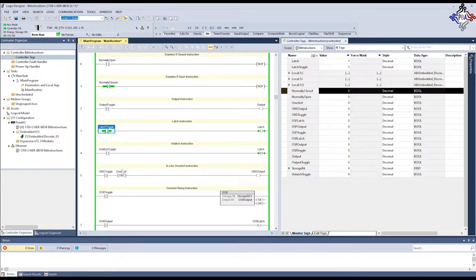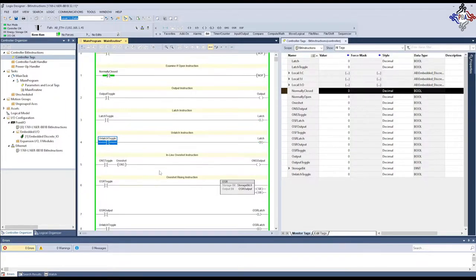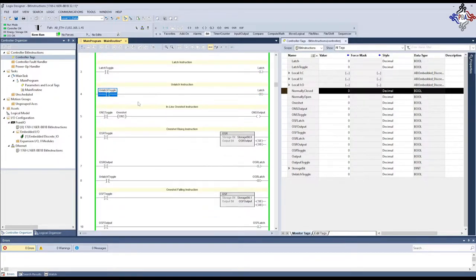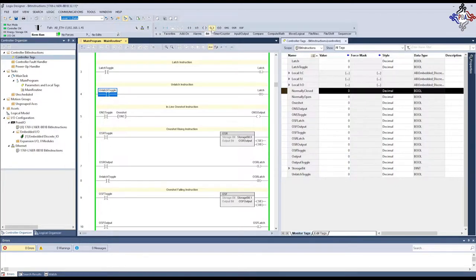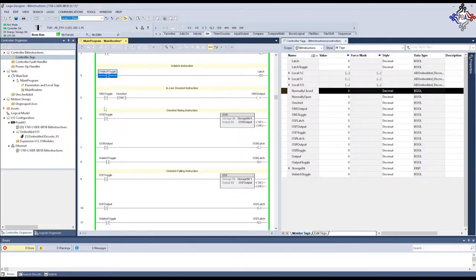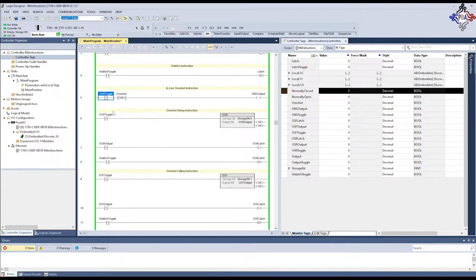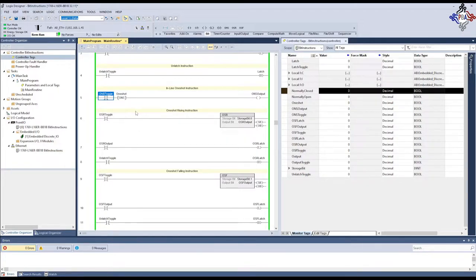Now, we're going to move on here. That's going through our examine on, examine off, output energize, output latch, and output unlatch. Now, these three are a little bit different. These are called one-shots. They only go true for one scan of the controller. So, if I turn this on and then turn it off again, you don't see anything happen. Nothing appears to happen. Now, if I throw another rung in here, tie these together, and give myself an output latch.